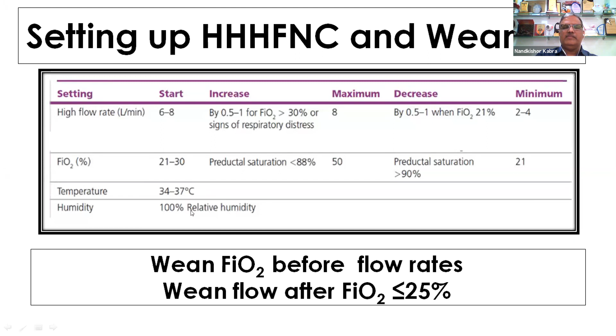So you would start with a flow of somewhere between 6 to 8 liters, and if the baby's distress is not settling, then you may increase the flow by 1 liter, up to a maximum of 8 liters per minute. And FiO2 you'll start with 30 and maybe increase as required to as much as 50% or so. Once the baby is stable, when you are weaning, you need to wean FiO2 before weaning the flow, and you would get your FiO2 somewhere close to 25% or so before you actually start weaning the high flow. The gas is administered at a temperature of 34 to 37 degrees with 100% relative humidity.